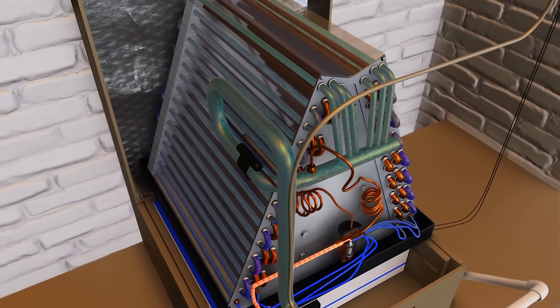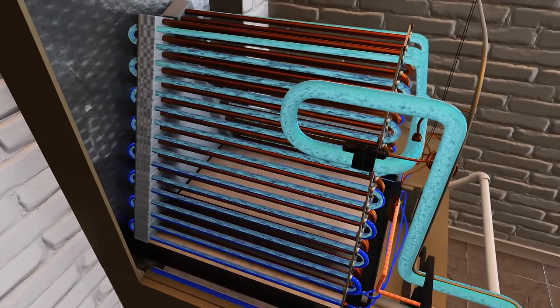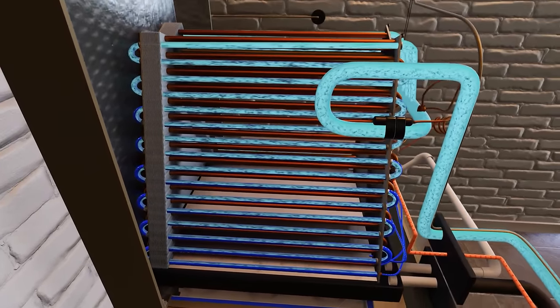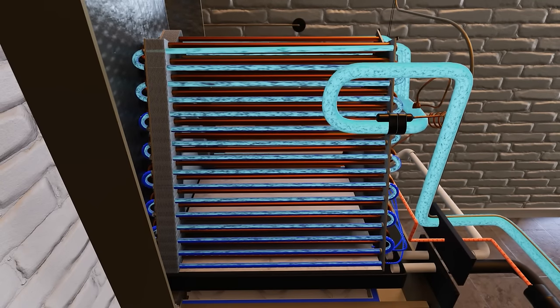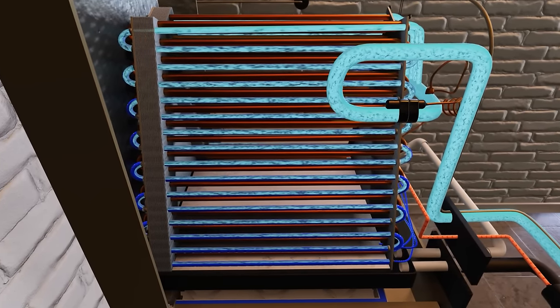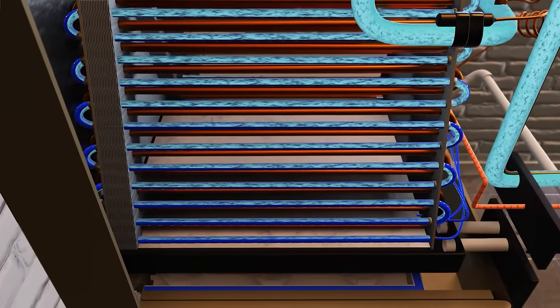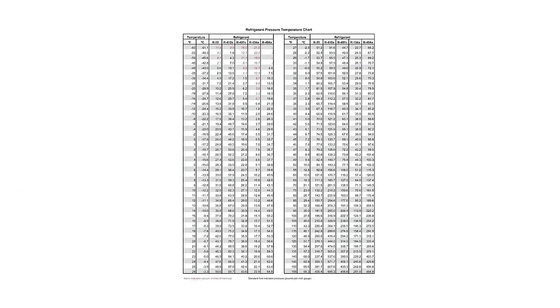When we think about an evaporator coil, there are two things we really want to know. One is: what is the temperature of the refrigerant boiling in the evaporator coil? We call that evaporation temperature or evaporating temperature. And how do we know what that is? You take that suction pressure, you look at the scale for the refrigerant you're working on, and it gives you the temperature — that's suction saturation.